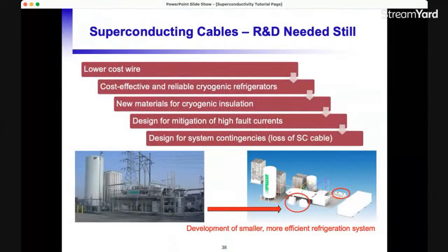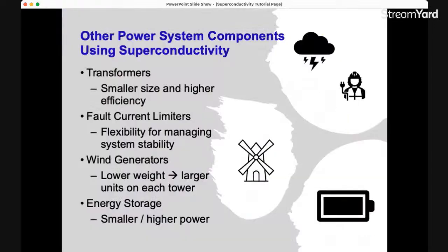Here we talked about the cables, R&D needed. We talked about lower cost wire. Refrigeration needs to be made more efficient and more reliable. New materials for cryogenic insulation are needed. We need ways of mitigating high fault currents, especially for DC cables. And then there's the system contingencies, the loss of the superconducting cable. These are some of the things that are still needed.